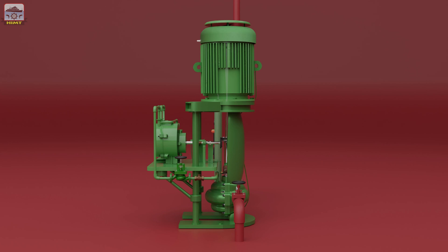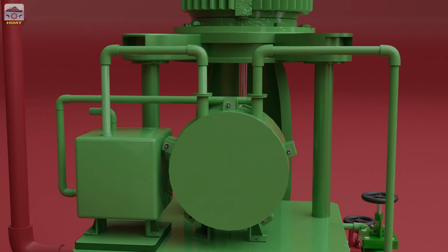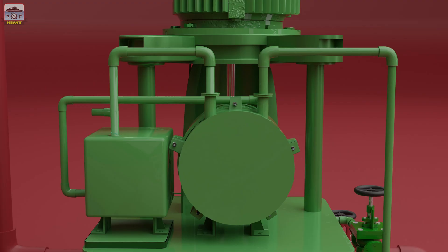On emergency fire pump and cargo discharge pumps of centrifugal type, since the regulation permits the use of fitting the emergency fire pump within 4.5 meters above the minimum water line, this pump must be fitted with a self-priming pump.